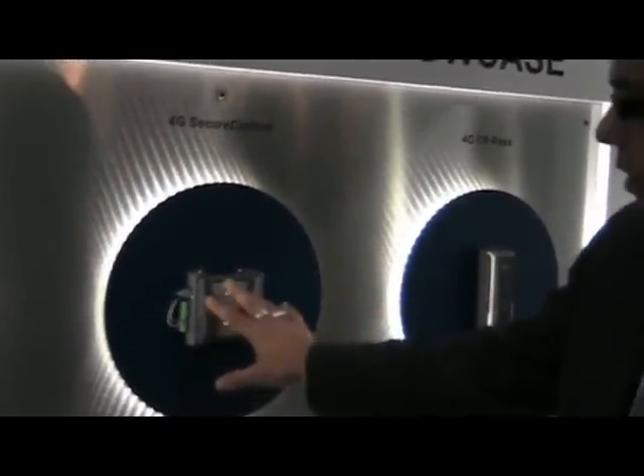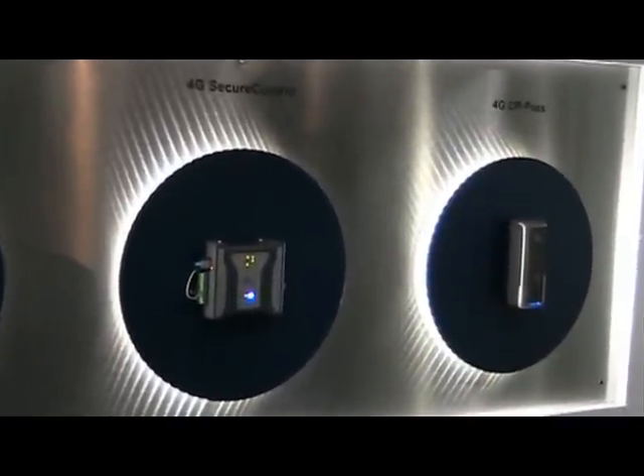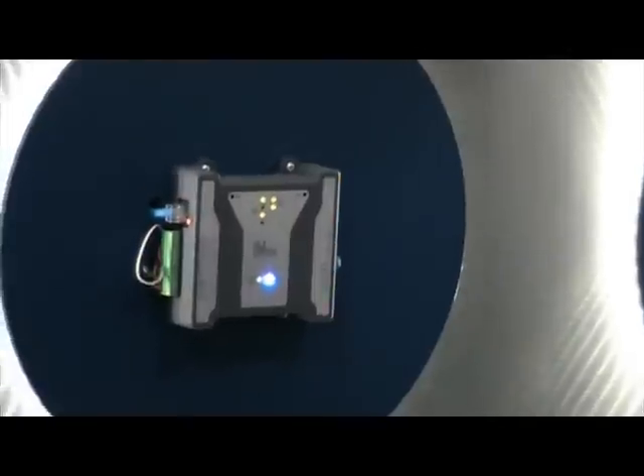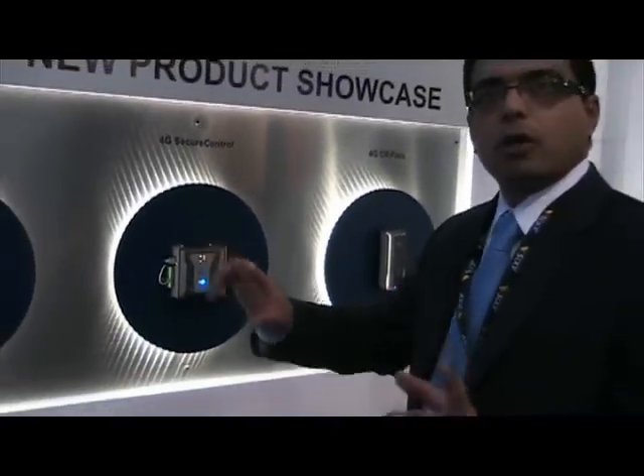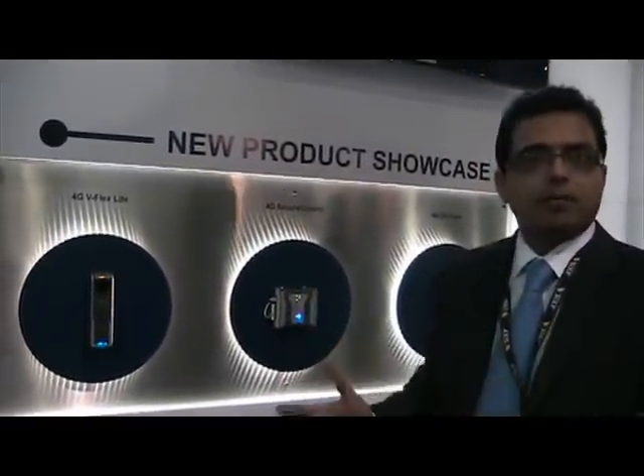From a security perspective, as part of this product suite, we are also coming out with a controller called Secure Control. This is not meant to compete with an access control panel. The purpose of this controller is to provide security of the door control on the secure side of the door — you would install this behind the door, and this product sits in front of the door. The communication between this device and the Secure Control is encrypted 485.